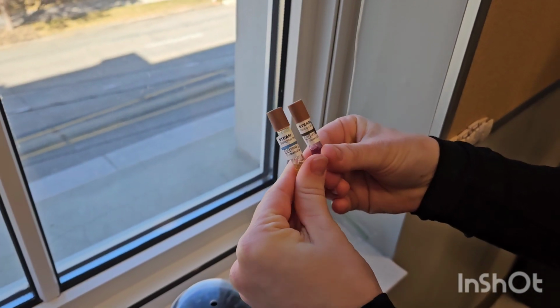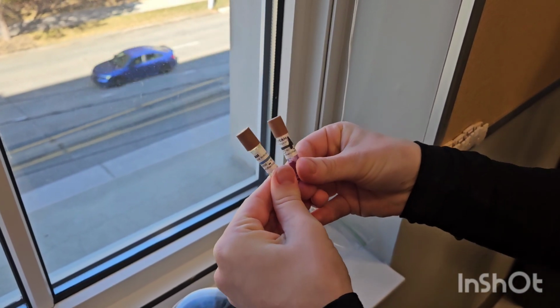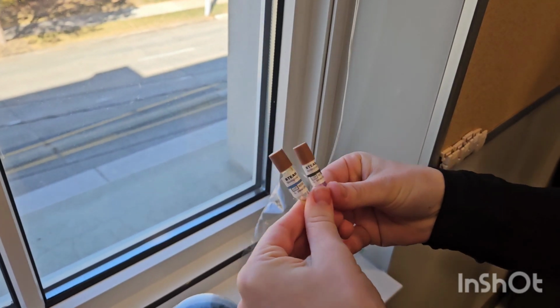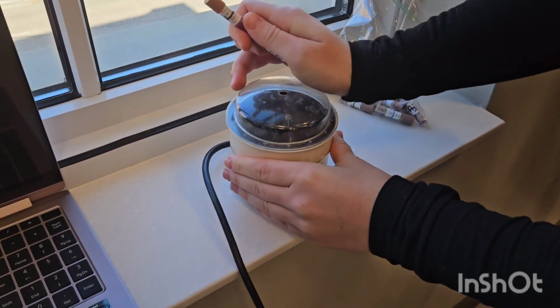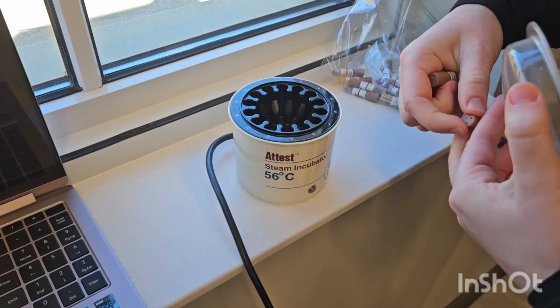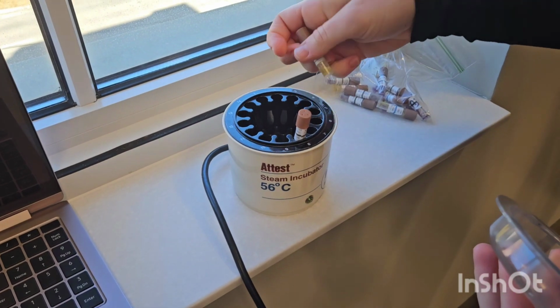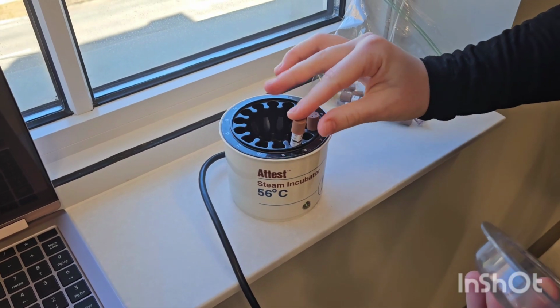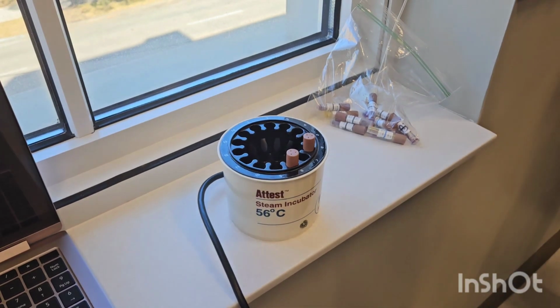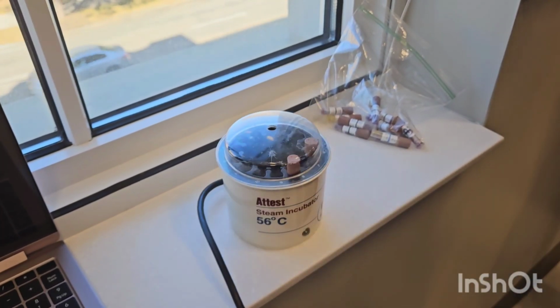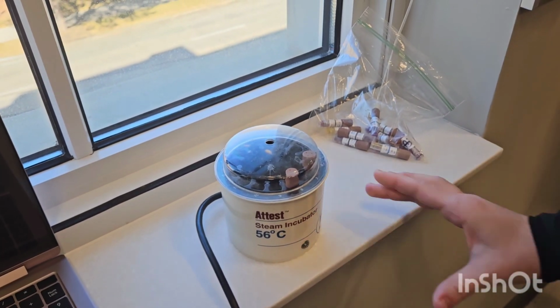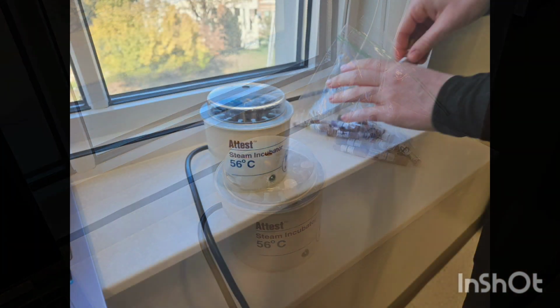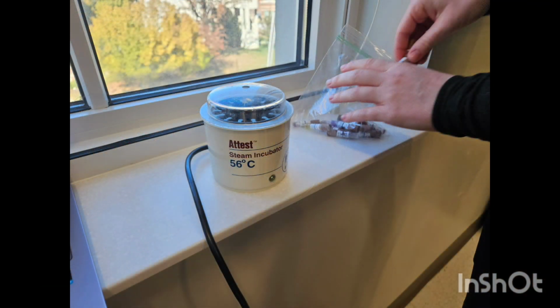Routinely use physical and chemical monitoring. Biological monitoring is the only way to be sure that sterilization has occurred, and testing must be done weekly to ensure sterilizers are working properly. 2 types of biological indicators are used for spore testing. Geobacillus stearothermophilus is used for testing steam, chemical vapor, and hydrogen peroxide sterilization. Bacillus atrophaeus is used to test dry heat or ethylene oxide gas sterilizers. Biological indicators come in the form of spore strips or self-contained vials.